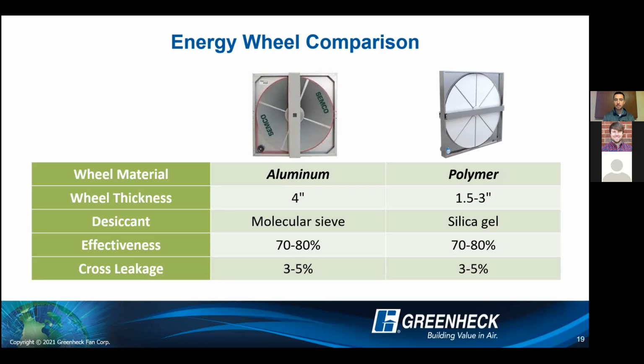From a desiccant standpoint, so what is doing that latent energy or that humidity transfer, the aluminum wheel has a molecular sieve, and I'll talk about the application here in a couple slides. And the polymer wheel is going to have a silica gel desiccant, similar to what you'd see in those white packs, the do not eat packs in beef jerky, new pair of shoes, things like that. Effectiveness, really going to be similar across the two wheels, 70 to 80% enthalpy recovery ratio. And then from a cross leakage standpoint, looking at about 3 to 5%.